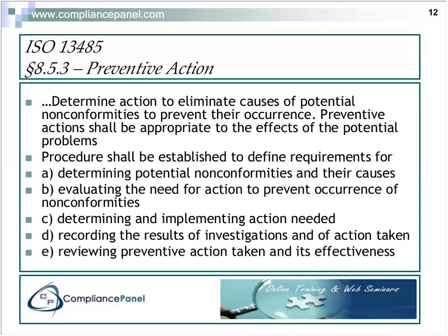I used to ask myself why the drafters made it a point to include this. Why couldn't they just title 852 Corrective and Preventive Action? I believe the reason they did this is intent. They want to make sure that you identify corrective actions and preventive actions and distinguish one from the other. Note that in the FDA regs, while both corrective and preventive action are included, they are not separately referenced. You want to make sure, if you need to be in compliance with 13485, that when you identify and then perform preventive action, to explicitly reference it as such.